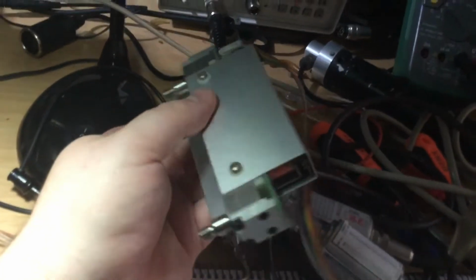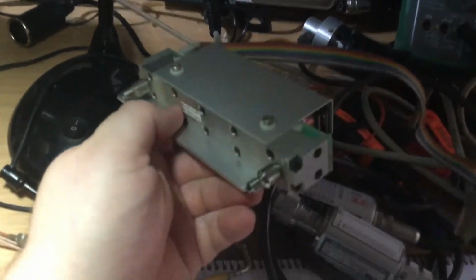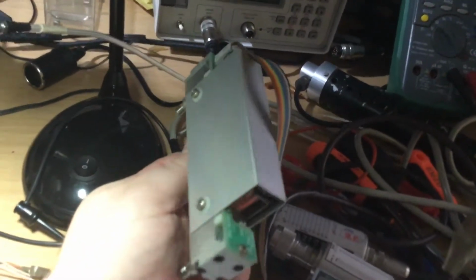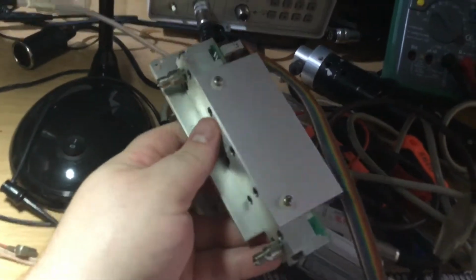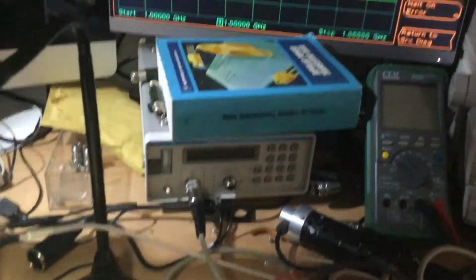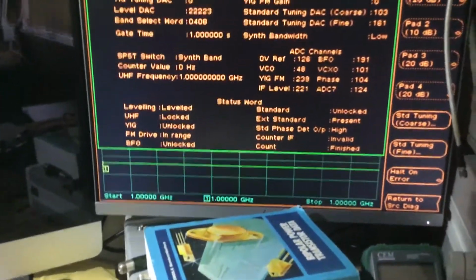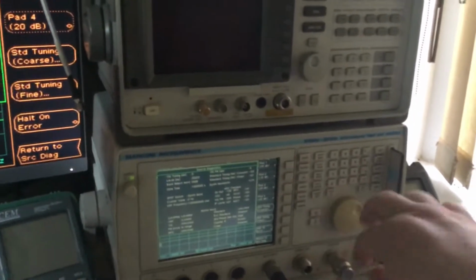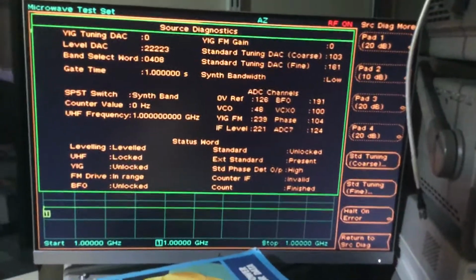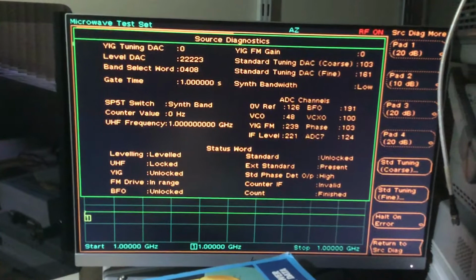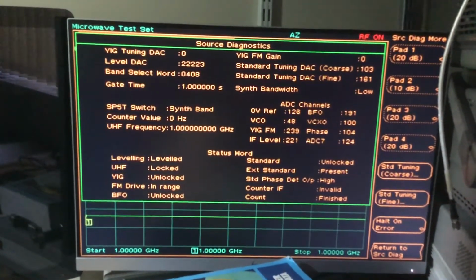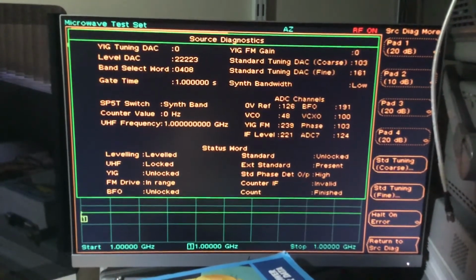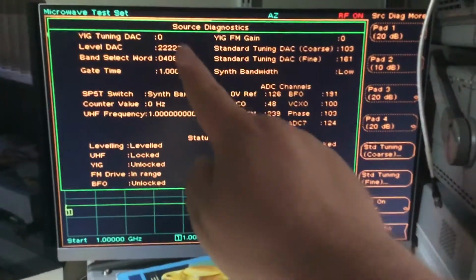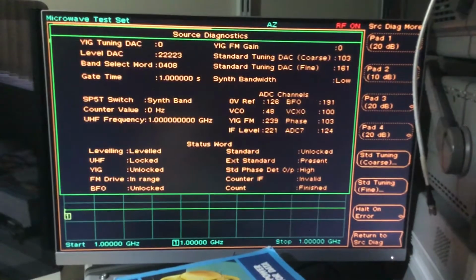And so this is the step attenuator module. You'll find these in most radio test sets, don't matter whether Marconi, HP, Agilent or Rohde & Schwarz, they all use this type of mechanical switched pad attenuator that switches in different attenuation pads. So that's just a little rundown on the diagnostics menu. So obviously, when the RF output is coming out of this connector, there's a loop back, a sniffer, a sensor that sniffs back the RF, rectifies it into what appears to be a DC level, and then it feeds that back into an ALC circuit, which is compared against a reference, which is obviously what's stored in the level DAC here in memory for that particular power level, for that particular frequency.